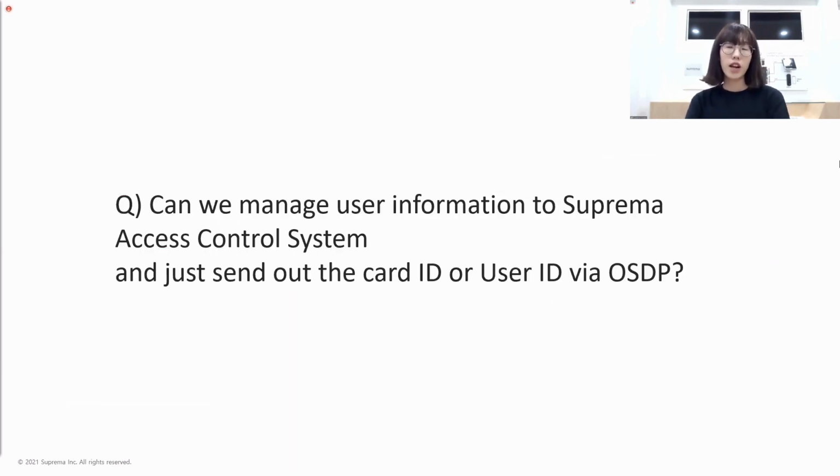Next is as follows. This is one of the most frequently asked questions. In the typical access control market, many customers are using Suprema devices as Wiegand output devices. Now, the number of inquiries about passing card ID or user ID through OSDP to the access control panel instead of Wiegand output is increasing. With BioStar 2 software version 2.8.10 and BioEntry W2, we support this feature.